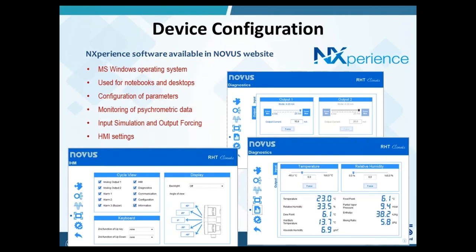The configuration of RHT Climate is an easy task. Novus offers a free Windows software available for download on our website called NXperience, which can be used on notebooks or desktops. It is a powerful tool for the technician commissioning the device in the field. All features needed for these activities are available in the software: configuration of all parameters, monitoring of all psychrometric data, simulation of temperature and humidity, forcing output transmission signal, and settings for the HMI display. Here are some example screens from NXperience.